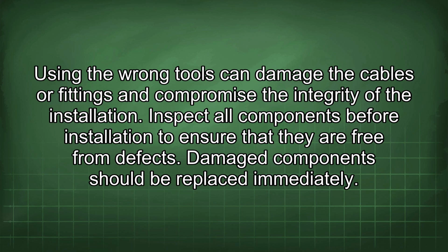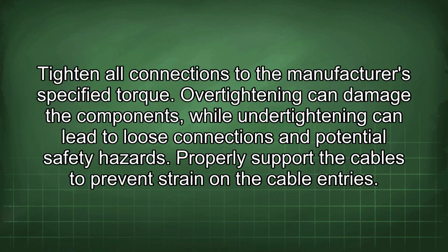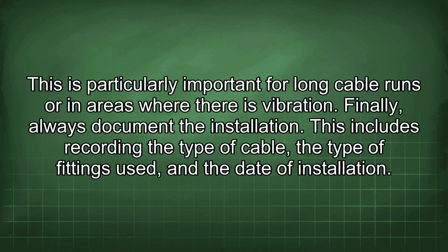Inspect all components before installation to ensure that they are free from defects. Damaged components should be replaced immediately. Tighten all connections to the manufacturer's specified torque. Over-tightening can damage the components, while under-tightening can lead to loose connections and potential safety hazards. Properly support the cables to prevent strain on the cable entries. This is particularly important for long cable runs or in areas where there is vibration.